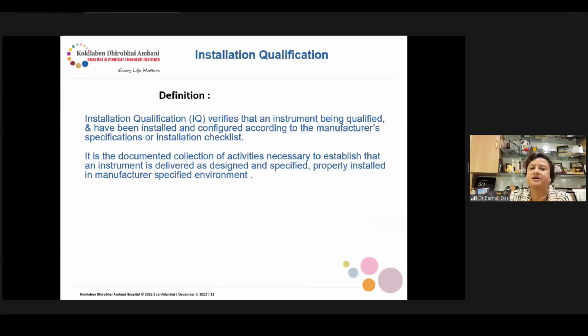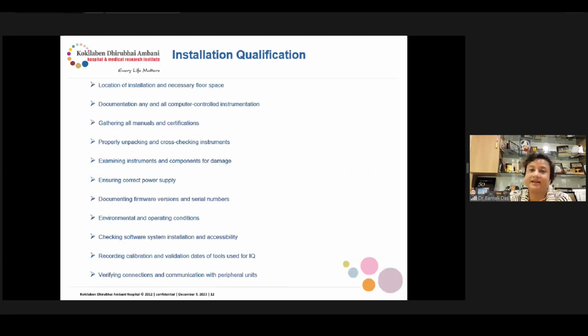So IQ verifies that the instrument being qualified has been installed and configured according to the manufacturer's specification. It is a documented collection of activities necessary to establish that an instrument is delivered as designed and specified, and that it is properly installed in the manufacturer-specified environment. So what should be the checklist?